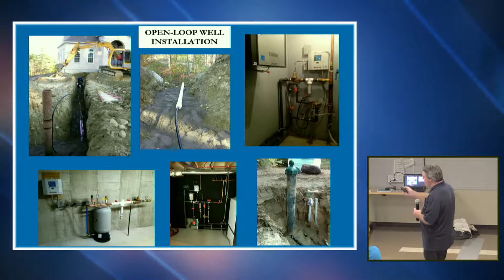This is some open loop pictures where we'll take the existing water well and extract the heat from the water in the well, and then we put it back to the well, and we have what's called a bleed, which is the white pipe that you see. What we'll do is we can use the aquifer to keep the temperatures up in the water by bleeding some of the water off as long as you have a place that you can get rid of water.